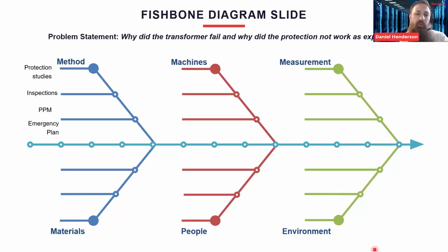Protection studies, there was one done, Johnny. There was one in place. It had been done maybe 18 months prior, but there had been some changes on the network in another area, so it wasn't fully up to date, but it would have been updated once that project was finished. But you're totally right in what you're saying. That's why we repeat them, because if there are changes on the network, we need to know that can impact the fault levels, and at the same time, we need to verify the utility supply, so the DNO, that if they've made any changes that might impact the downstream network, we take them into account.